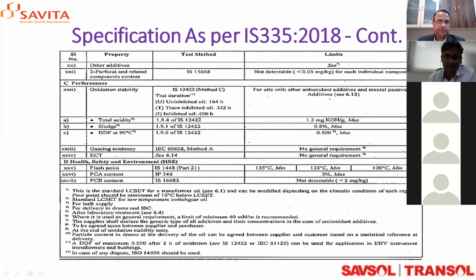Essentially, I think Abhay must have already answered the question, though I can't read his answer. Essentially, wherever there is ingress of oxygen or air into the transformer, if that is possible, then unfortunately we cannot use it, because that would mean contact with air, and over a period of time that would lead to oxidation.